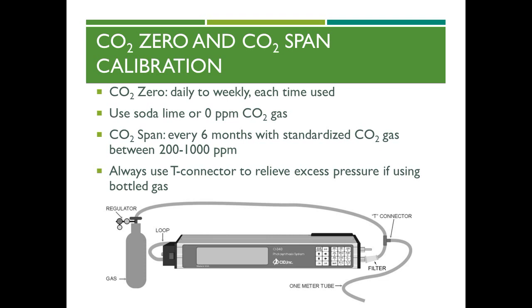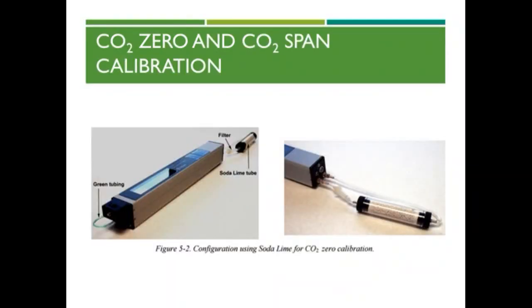A full span calibration utilizing a known CO2 gas standard in the range of 200 to 1000 ppm should take place every 6 months, depending on frequency of use. For gas flow regulation during span calibrations, connect the standard gas to the CI-340 and use a T-connection valve to help regulate pressure. Soda lime, which is a scrubber for carbon dioxide, can be used on closed loop for zero calibrating the CO2 sensor, seen here.